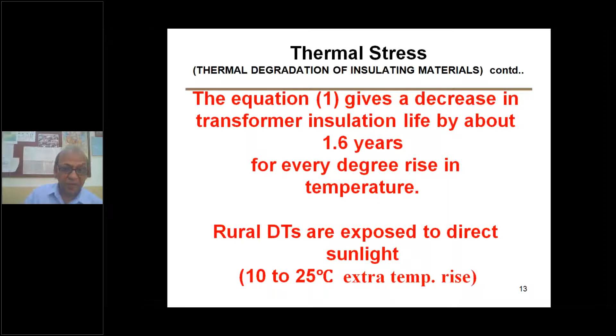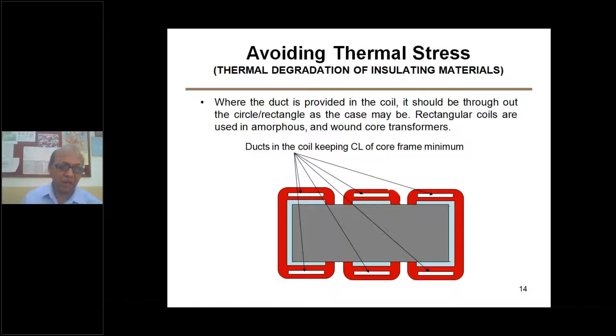Therefore, we can expect the failure rate because of the thermal stresses. Now another thing is, you are getting transformers nowadays manufactured, let us say, maybe amorphous or foil type. In that case, you provide the duct for cooling. Only two sides ducts are provided. Other side, inner side ducts are not provided. This transformer will pass the heat run test, but hot spot will be high, and we are not measuring the hot spot directly, we are just calculating. So this is also a cause of the poor reliability of this type of transformers.